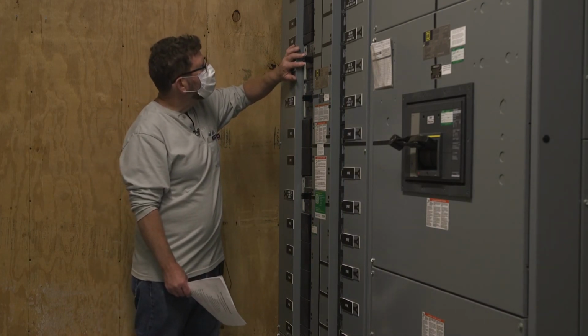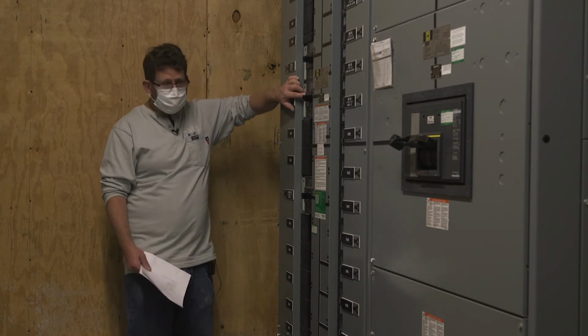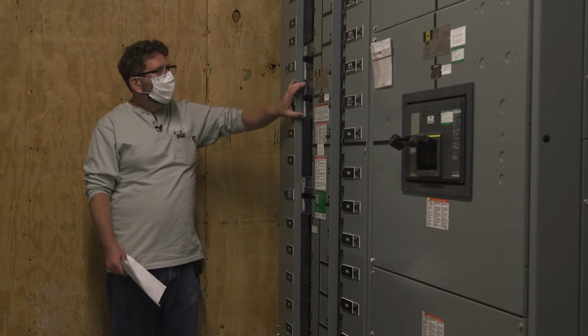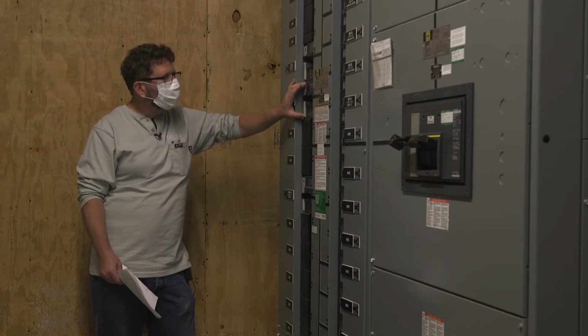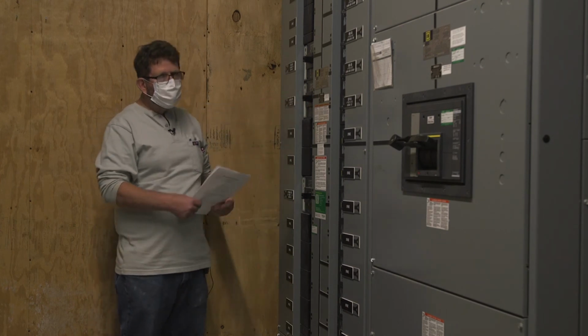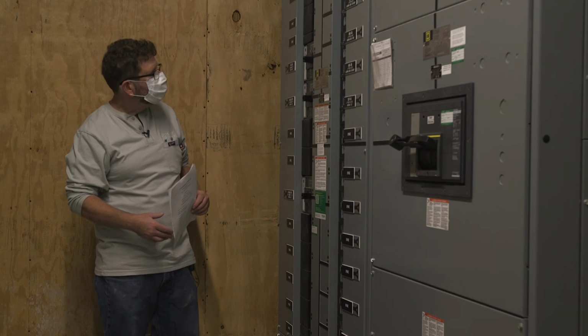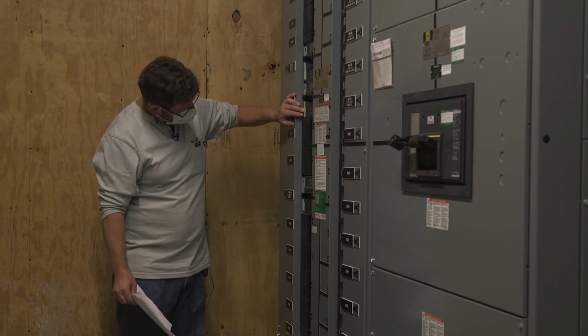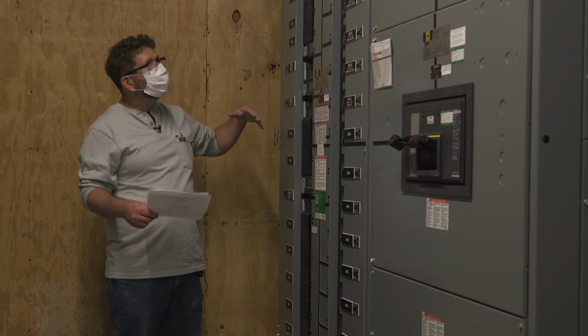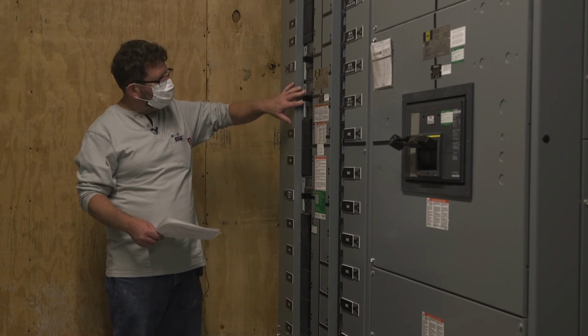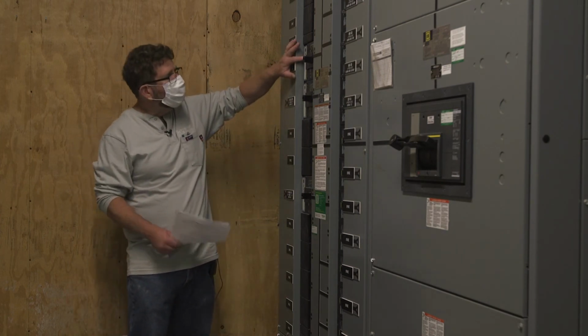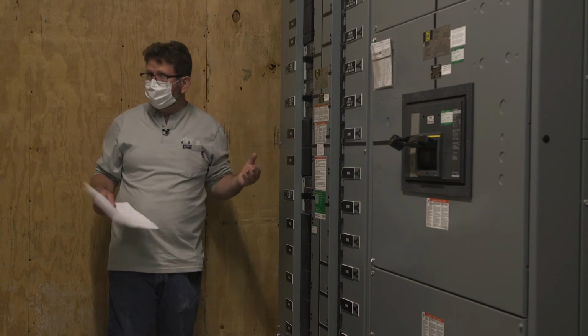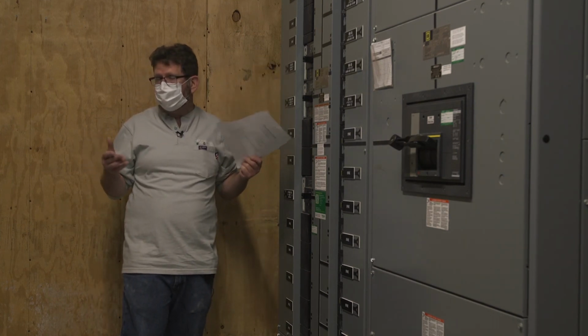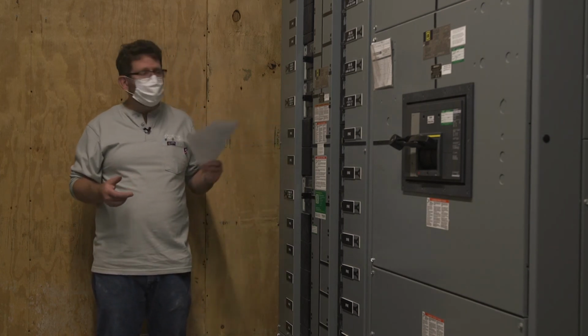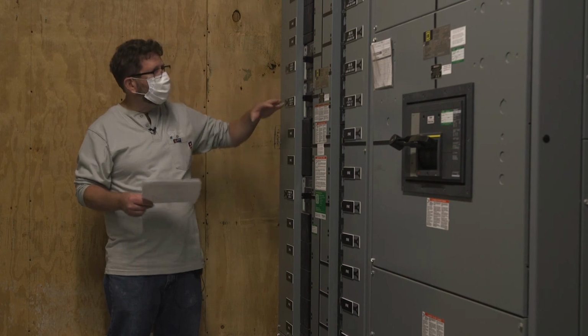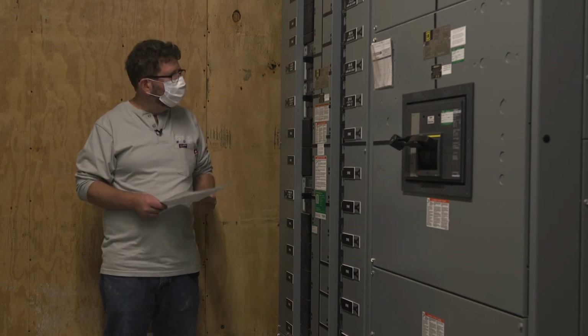Here on these, you can see the trip units. Notice the little green lights flashing here occasionally. The power for the trip units, for the microprocessor in the trip unit, comes from current going through the breaker. So as long as you have about 10% load going through the breaker, the electronics of the trip unit will power up and you'll have that green light. If you don't have the green light, it's not necessarily a problem. But if you know it's carrying 10 or 20% load or more, and you don't have the green light, that would be indicative of a problem. For some reason the electronics aren't powering up. But if you don't have any load through it, the green light's not going to be on.